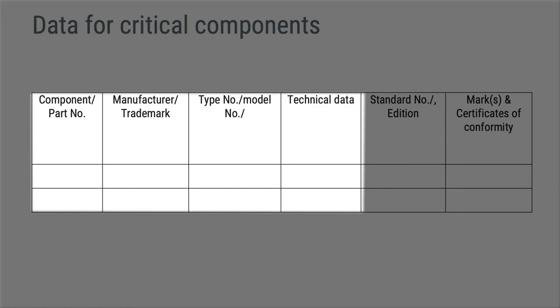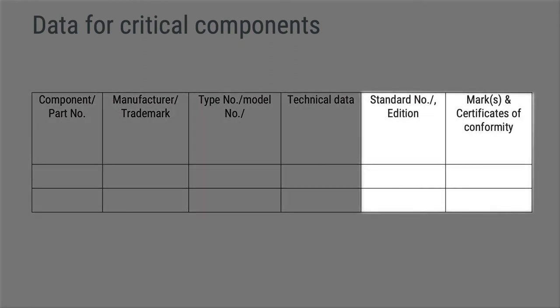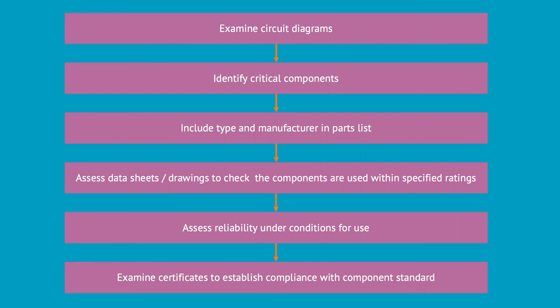For each critical component, you shall identify the part number, manufacturer, type number, and technical data in order to uniquely identify the component. You shall also identify which standards the component complies with and the reference number for the certificate of conformity or test report. Remember to check that the standard is suitable for the component and that a valid edition has been applied. Always check the certificates of conformity for every critical component and any limitations indicated on the certificates.